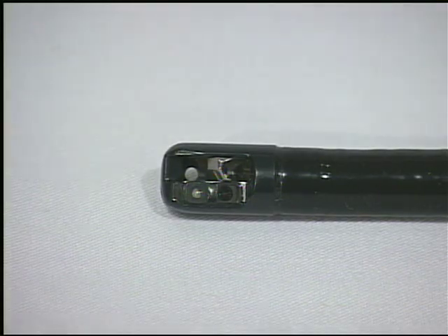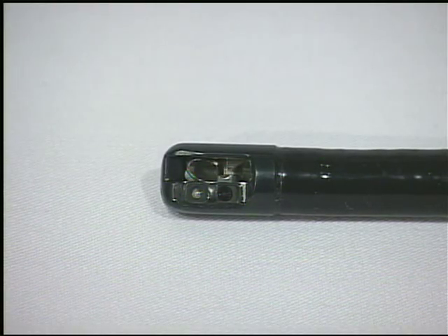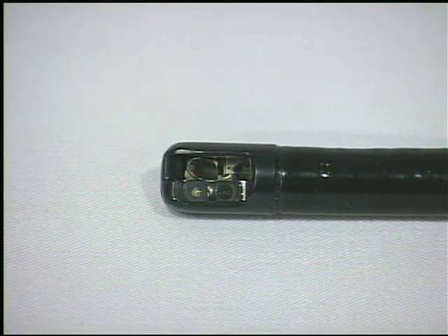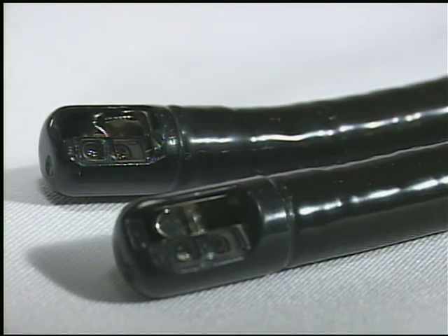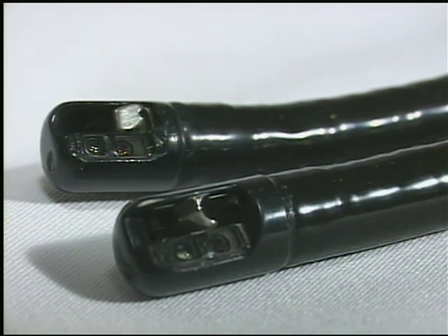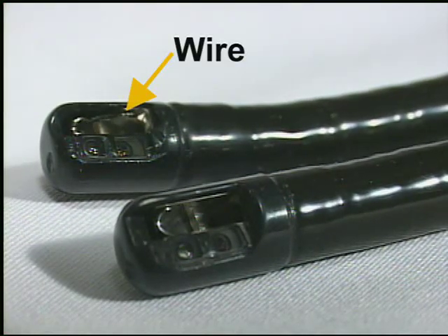Other features: elevator mechanism. Traditionally, endoscopes such as side-viewing duodenoscopes with elevator mechanisms and exposed elevator wire channels have been considered the most difficult to properly reprocess and pose the greatest risk of infection to patients, especially those whose immune systems are compromised. Conventional elevator mechanisms are controlled via a control wire, which travels the entire length of the insertion tube. Due to the very limited amount of space between the elevator control wire and the internal channel it's housed in, higher than usual pressures are required to inject reprocessing agents into this area.